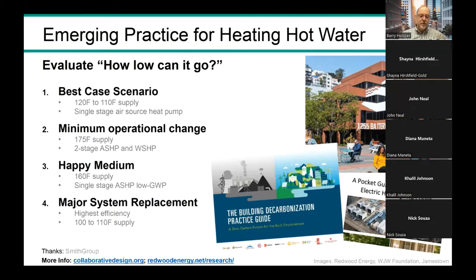There are four different examples highlighting water temperatures as low as 120 or 110 degrees, enabling continued operation of a similar system that can be the lowest cost option with the least redesign necessary, since those temperatures are compatible with the most common types of air source heat pumps, whereas 175-180 degrees is not really necessary.